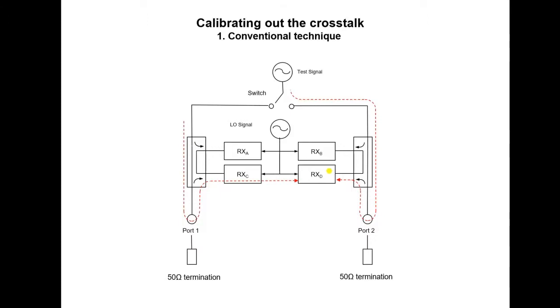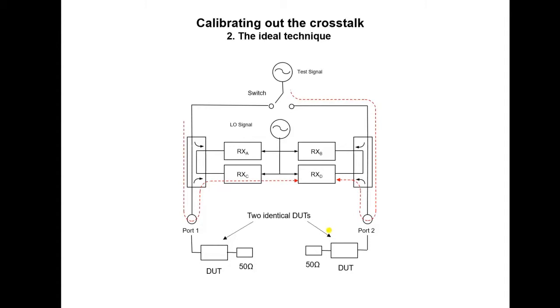Let's look at another approach. Here, we have what we can refer to as the ideal technique. What we do here is to use the actual device to be tested as the termination for ports 1 and 2 during the crosstalk calibration step. This works very well, but the disadvantage is that you need two identical devices which can be quite difficult to achieve. Not impossible, but it is difficult.